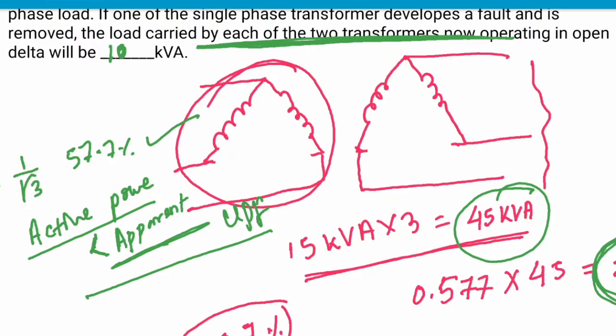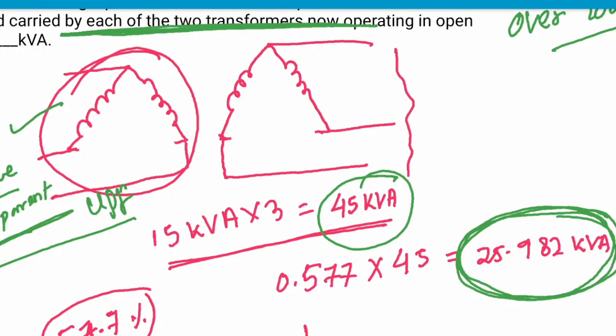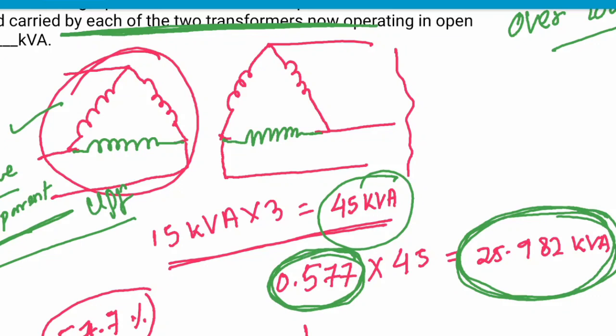And when this is used, if one transformer is faulted and taken out for repairing, the condition is that the load should be less than the reduced capacity. Reduced capacity is 57.7% of the full capacity. If the connected load is less than the reduced capacity, then only we can use the open delta method. And this is generally not a general condition. Generally three transformers are used for three-phase load supply, because the efficiency reduces to this much. So why would this be used for general purposes? So this is the end of this question. Thank you for watching up to here.